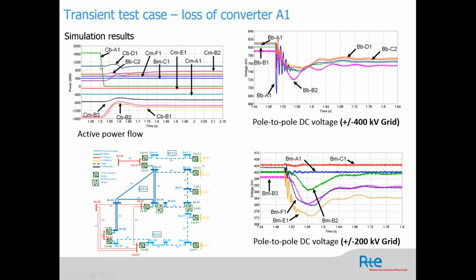So what's happening here? Let's start with the green one. This is the station that is tripped, so it goes suddenly from 1,600 megawatt to 0. As I mentioned before, since you have a droop control in your system, the other stations will automatically adjust their active power in order to compensate for this power loss. You can see that CBB1 and CBB2, so this one and this one here, will act as an active primary control to adjust the active power. However, CBD1 stays constant. You have some slight disruption, but at the end it stays constant.